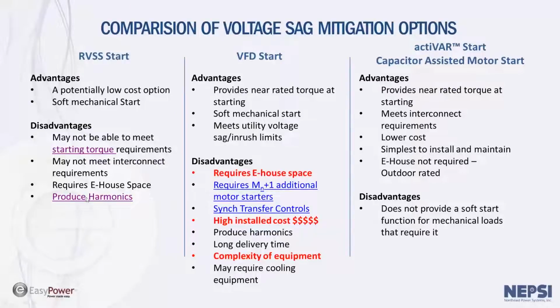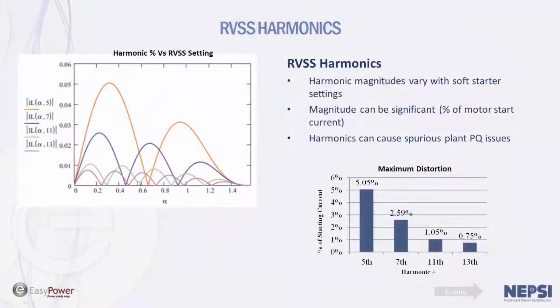Soft starts also produce harmonic currents. If I click on the slide, you can see that depending upon the phase angle operation of the soft start, it can produce harmonic currents. The graph here shows the orange curve for the fifth harmonic. You can see as the phase angle of the soft start is varied between 0 and 1.4, it will produce harmonic currents based upon its phase angle of operation. Throughout its operation, it could have a maximum fifth harmonic current of 5.05%, and that's 5.05% of the starting current at that point of operation. So it can be quite significant.